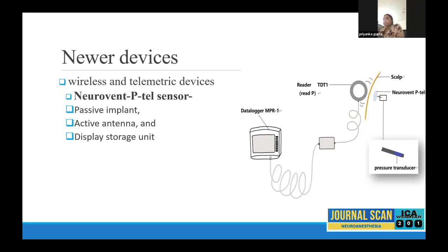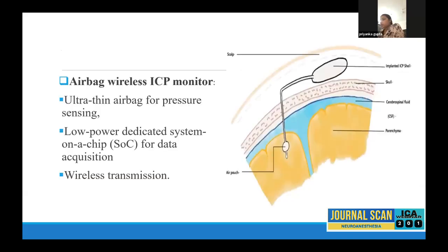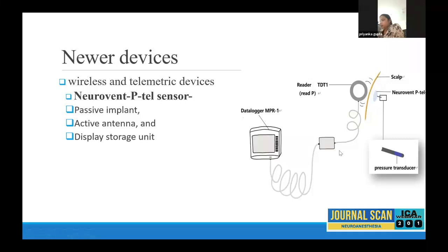One of the sensors I will talk about is the Neurovent P-tel, meaning the telemetry sensor. It is a passive implant. The implant is inside the brain, and that blue tip is a sensor. Then there is an active antenna, and then this is the display or storage unit. They are not connected. Once it is inserted, the sensor remains inside the brain, and the signals are captured by radio frequency signal. So ICP is monitored and transmitted by radio frequency. An even more advanced telemetric version is one where you put the sensor in the patient and forget it, and on a mobile you can see the ICP of the patient. These devices are in the process of development.